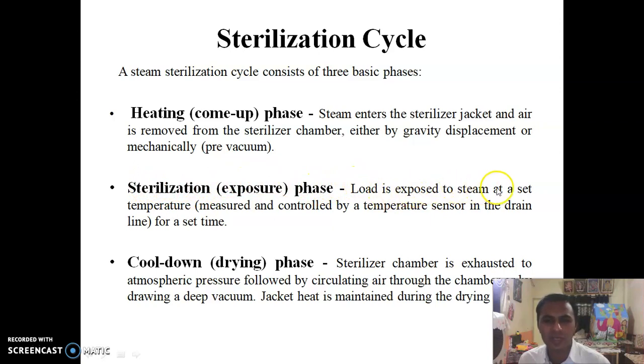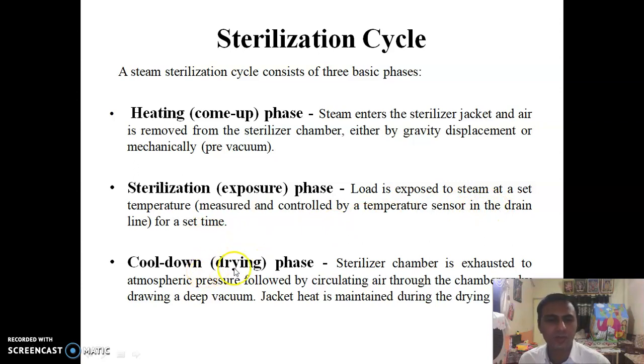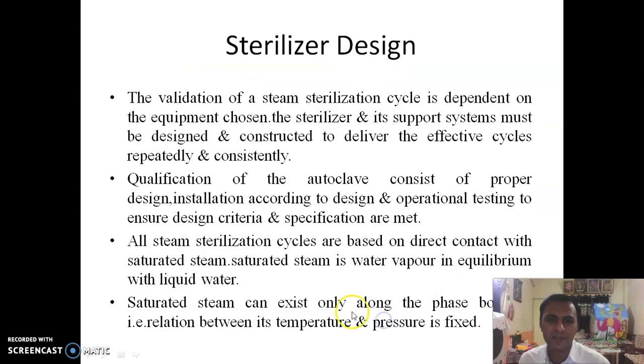During the sterilization phase, the load is exposed to steam at a set temperature, measured and controlled by a temperature sensor in the drain line for a set time. The cool-down and drying phase follows: the sterilizer chamber is exhausted to atmospheric pressure, followed by circulating air through the chamber or by drawing a deep vacuum. Jacket heat is maintained during the drying phase.